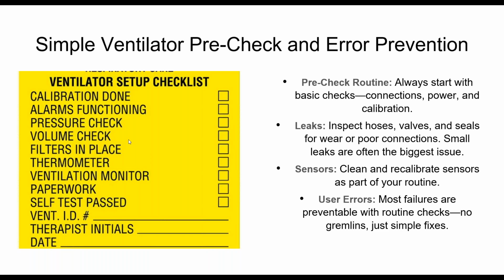These are more in-depth for the biomed. The hoses are something that somebody can visually look at from the outside, but valves and seals are things you check when you have scheduled maintenance, or if you've got a repair invasive enough that you could check the adjacent components. Inspect those valves and seals, see how they're wearing, see if they're clean, see if there's medication crystallizing on some of these components because it has found its way through that flow path.